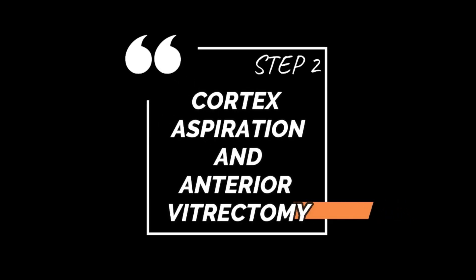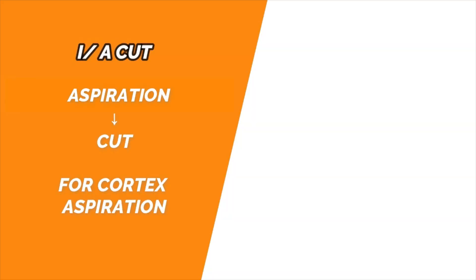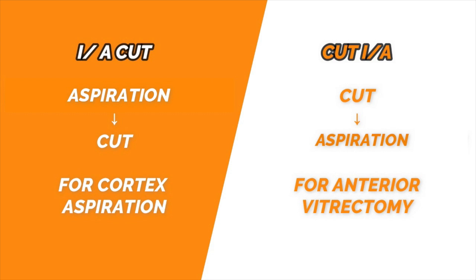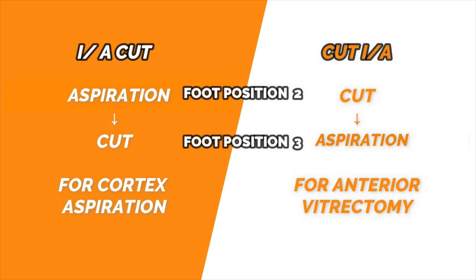Before proceeding with anterior vitrectomy, it is useful to understand the two modes of vitrectomy: IA-cut and cut-IA. In both modes, foot position 1 is irrigation. In IA-cut mode, foot position 2 is aspiration followed by cutting in foot position 3. In cut-IA mode, foot position 2 is cut followed by aspiration in foot position 3.